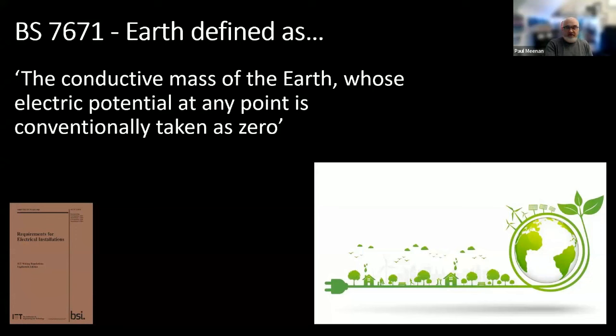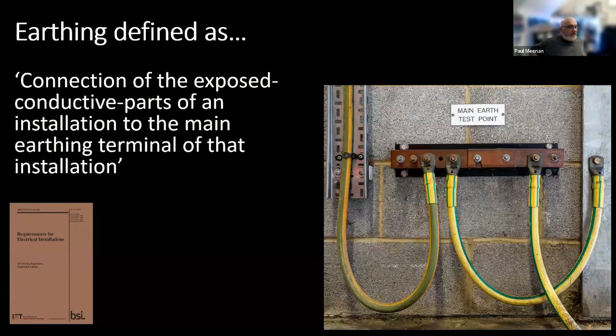7671 defines Earth as the conductive mass of Earth whose electric potential at any point is conventionally taken as zero. Now, potential is a word that we love to use in standards. What does potential mean? Voltage. So the voltage is conventionally taken as zero. So, this works. Earthing is the connection of exposed conductive parts of an installation to the main earthing terminal of that installation.